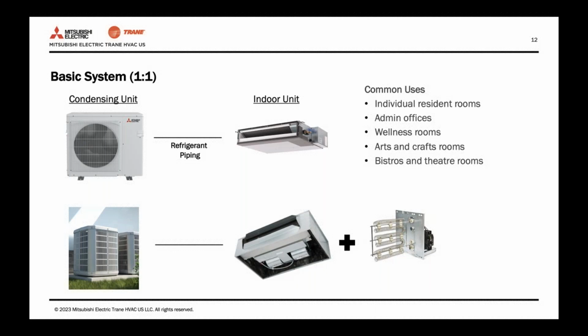First, the electrical amperage breaker size needed for the top variable capacity heat pump is 25 amps. The electrical amperage breaker size needed for the bottom split DX with the 8 kW heat kit is 75 amps, 3 times higher. Since breaker size is not the total picture, let's look at the two systems' MCA, or minimum circuit ampacity, ratings. These are all standard ratings for systems. The variable capacity heat pump has an MCA rating of 20 amps. That's for both the outdoor unit and the indoor unit. The split DX with electric heat has an MCA rating of 59 amps. Again, almost 3 times higher.